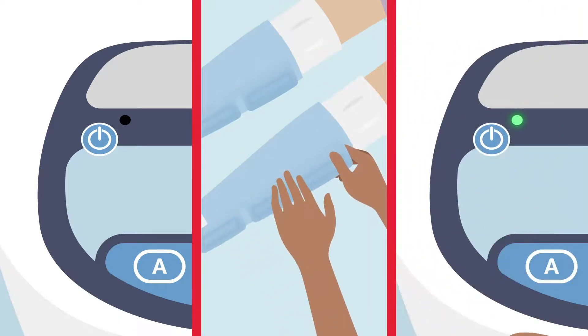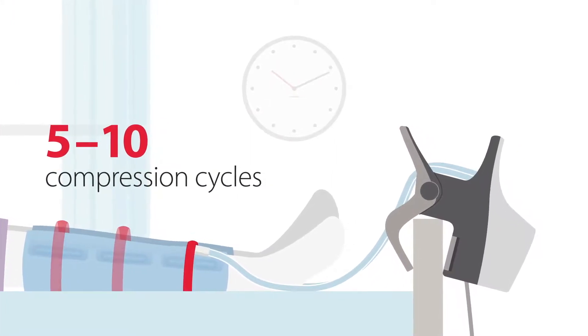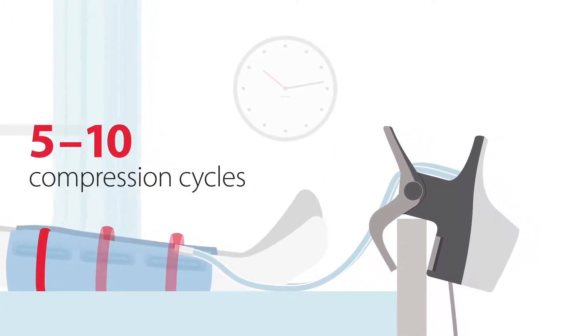Similar to the previous device startup, it will take the controller 5 to 10 compression cycles to determine the patient is there and resume the therapy timer.